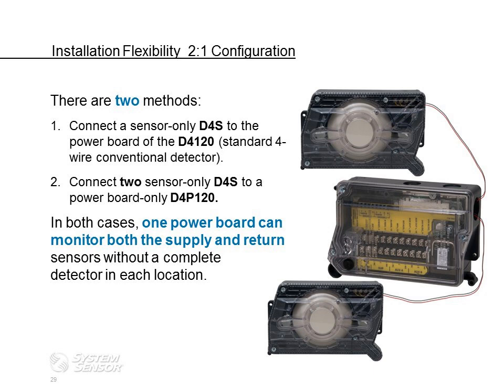So this can allow you to put your duct detector heads out in the ductwork and remote them back to a power board where you could actually mount that power board in a mechanical room or someplace else, which would allow you ease of wiring and maintenance and testing from the power board when you have space constraints out in the field on the ductwork.